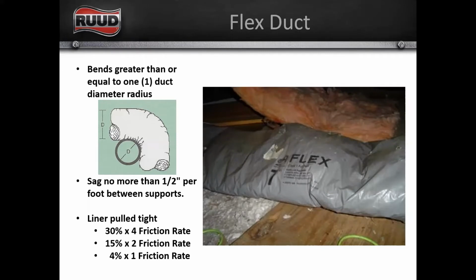And then finally, you want the internal liner to be pulled as tight as possible, right? Less than 4% compression on that. So you want to pull it very tight. And you can see that at 30%, we have quadrupled the friction rate. At 15% compression of that flex, we've got a 2 times friction rate, and at 4% is where we want to be. And that's pulling that duct really tight.